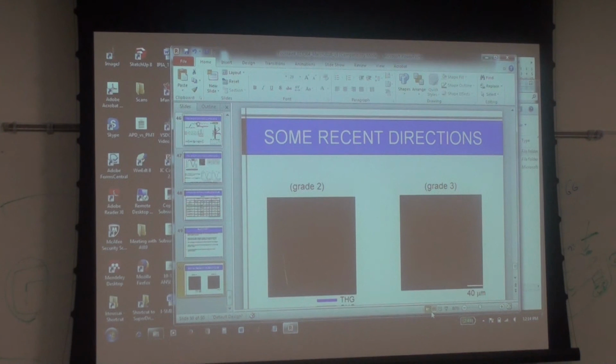So there's no risk of damaging? So I didn't put a slide in here. So what happens is there's a sweet spot. And so we work with 100 femtosecond pulse width. And the rep rate, so the distance between pulses, is going to be on the order of 80 megahertz. So if you have pulse widths that are somewhere between 80 femtoseconds to about 150 femtoseconds, you're right about a sweet spot where you can get enough energy, enough of this 2-photon effect to see a good second harmonic signal.